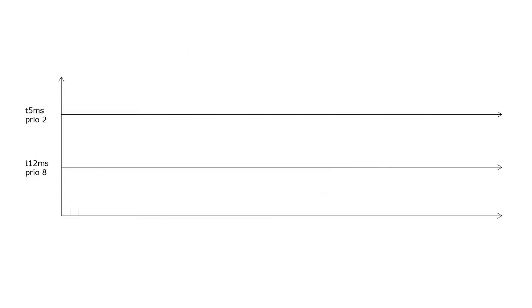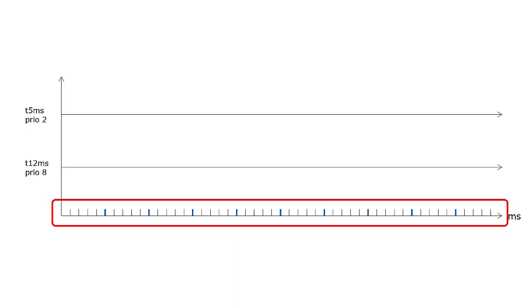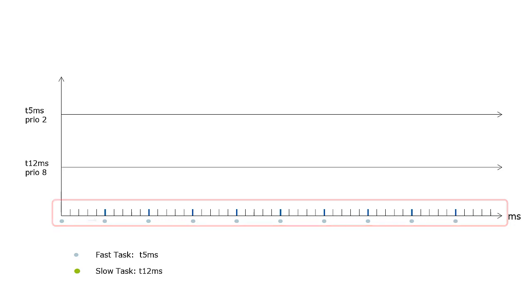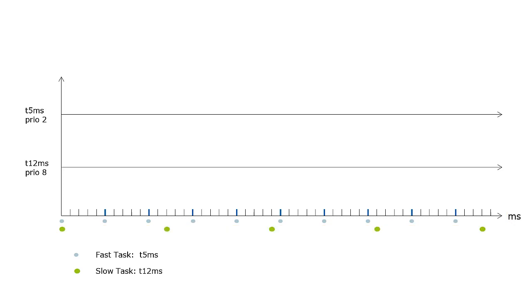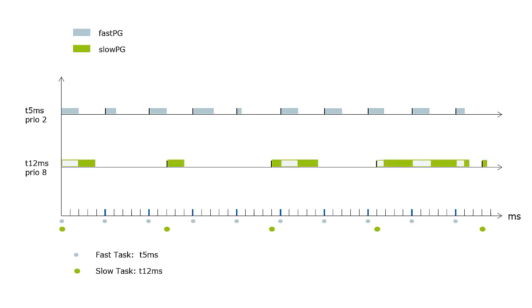The timing diagram shows that the system tick is set to one millisecond. The FAST task provides computation every 5 milliseconds, the SLOW task every 12 milliseconds. The programs FAST-PG and SLOW-PG are assigned to the respective tasks. They are executed in the context of the tasks.